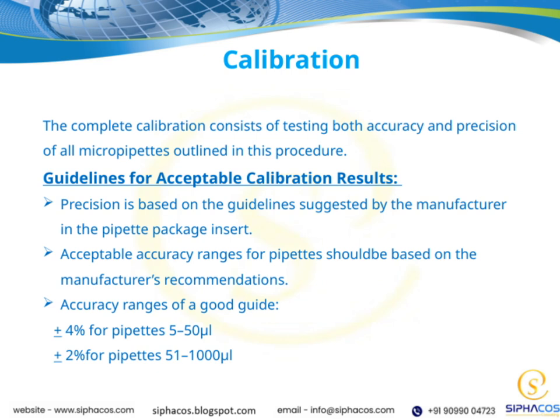To give you a general idea, for pipettes in the 5 to 50 microliter range, an acceptable deviation is about plus or minus 4%. For larger pipettes, say from 51 to 1,000 microliters, a plus or minus 2% deviation is considered acceptable. Understanding these ranges helps us ensure our pipettes are functioning properly, which is crucial for the reliability of our experimental results. Remember, calibration isn't just a routine, it's essential for maintaining precision and accuracy in our work.